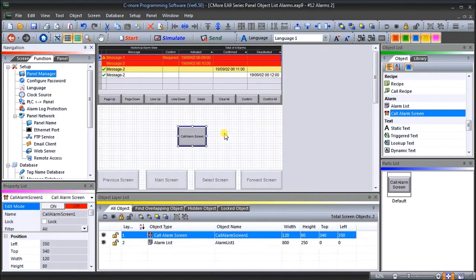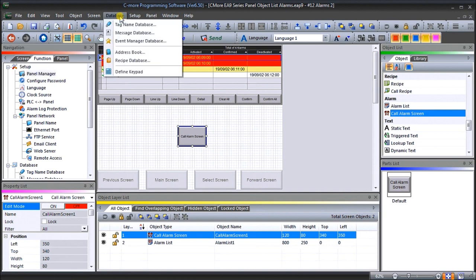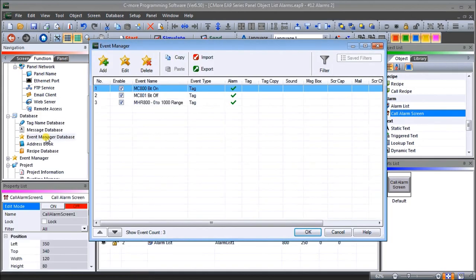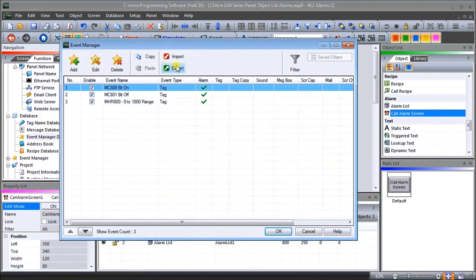Our actual alarms are programmed through our event manager database. That event manager database can be accessed through our main menu under 'database' — you'll see 'event manager database' — or under the function tab, go to 'database' and you'll see the event manager database. When we click it, we come up with the event manager window. This is a very powerful aspect of this HMI. We can add event managers to each of these systems, and what we currently have now is three alarms set up.